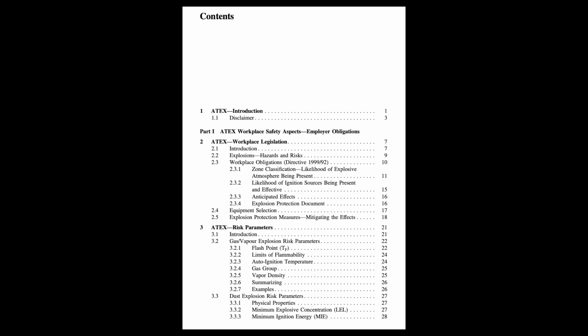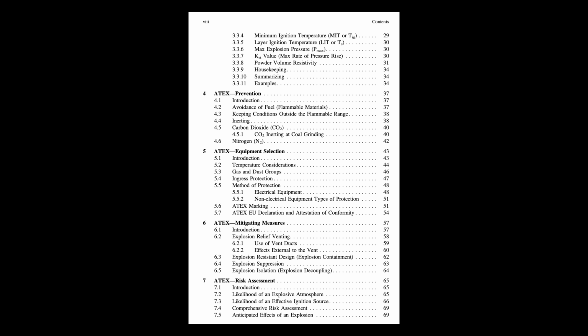The ATEX Equipment Directive specifies equipment categories, like Category 1, 2, 3, based on the level of protection they provide against ignition. The rule is simple. The higher the risk of an explosive atmosphere, lower zone number, the higher the required level of protection, lower category number. So Zone 0 or 20 needs Category 1 equipment. Zone 1 or 21 needs Category 2 or 1. Zone 2 or 22 needs Category 3 or 2 or 1.